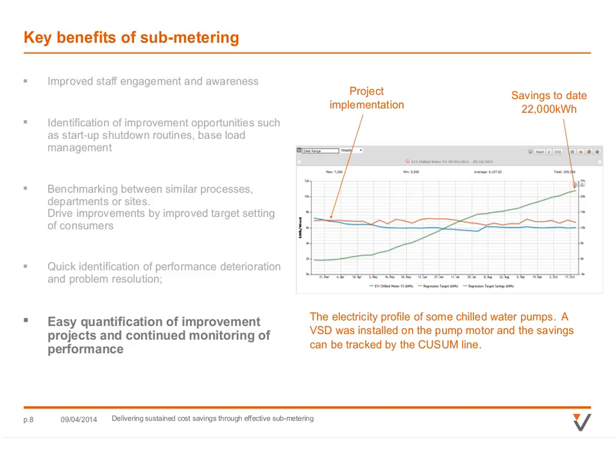We've used a CUSUM graph, which sums up the cumulative difference between these graphs over the time frame, so you can see at any point how much you've saved from where you expect it to be. It's a really good, neat way of making sure you've delivered the savings you expect, and also spotting if performance deteriorates. That's something I see a lot: new equipment put in, performance deteriorates, but you've assumed savings have been made.